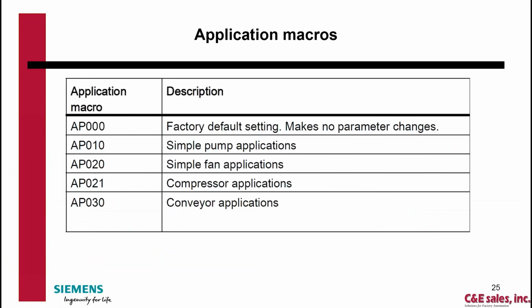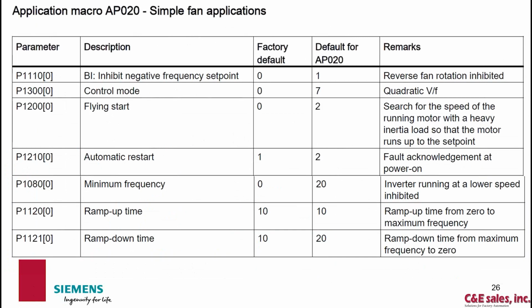Then there are application macros. For our example, we're going to use AP020 for our simple fan application. Then here are the parameters that AP020 is going to show. Reverse inhibited. It's going to be a quadratic volts hertz setup. Flying start enabled. Fault acknowledgement would be an auto restart. Here's your ramp up and down time that sets, based on common values for a pump. Minimum frequency of 20, ramp up time 10 seconds, ramp down time 20 seconds.